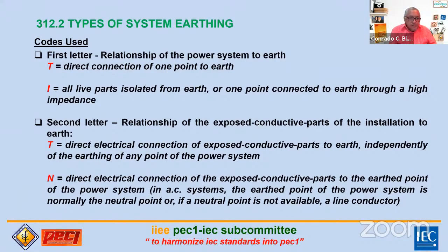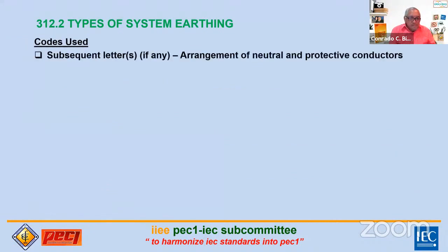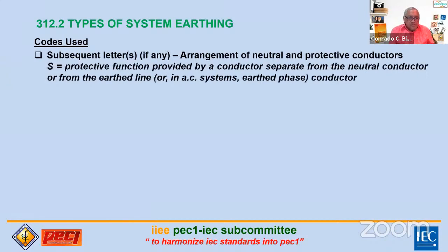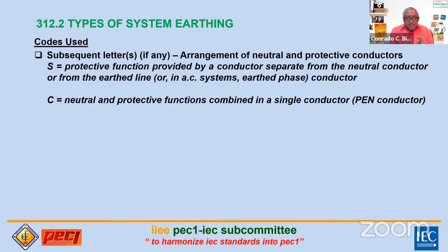There's a third letter, the subsequent letter, for the arrangement of neutral and protective conductor in the installation. S means the protective function is provided by a conductor separate from the neutral or from the earthed line, or in AC systems, the earthed phase conductor - meaning separate. And there's the C type, where neutral and protective functions are combined in a single conductor called PEN. Later we'll see the applications here in the Philippines since we follow the PEC requirements about the grounding system.